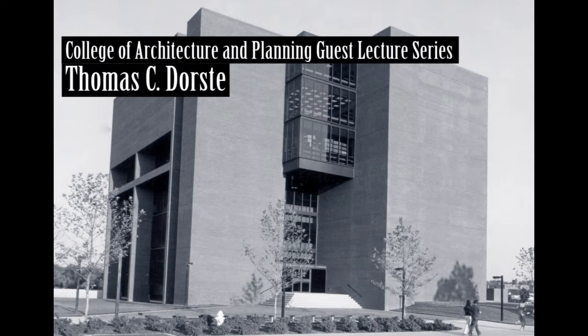In the course of the design, they asked us to study specifically, well, they said two things, which turned out to be 12 things. They gave us three high-efficiency collectors. And they said, we want you to study the use of those collectors mounted on the rooftops, because if you're familiar with the hospital in Indianapolis, it's roughly 8 stories high, and up and down, or mounted on the south side of the building vertically behind a glass skin so we can maintain it from the inside. And they gave us the three collectors. They gave us two locations. Well, when you multiply all that out, you've got a zillion studies to do.